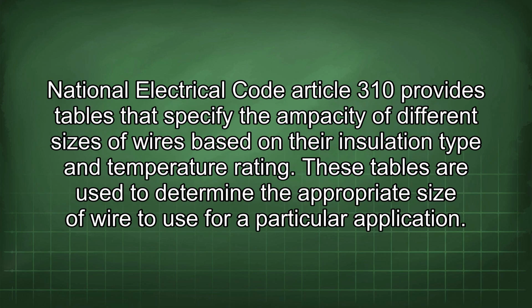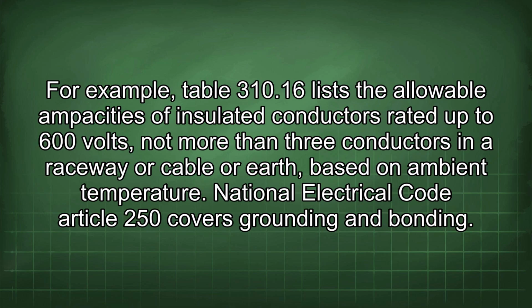National Electrical Code Article 310 provides tables that specify the ampacity of different sizes of wires based on their insulation type and temperature rating. These tables are used to determine the appropriate size of wire to use for a particular application. For example, Table 310.16 lists the allowable ampacities of insulated conductors rated up to 600 volts, not more than 3 conductors in a raceway or cable or earth, based on ambient temperature.